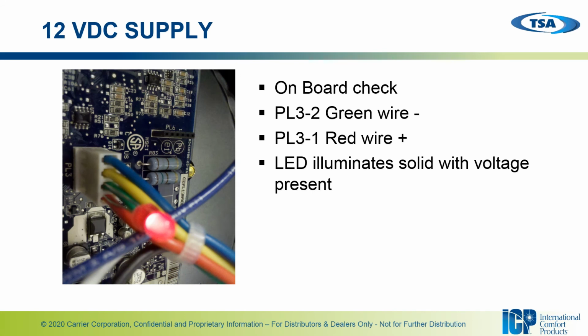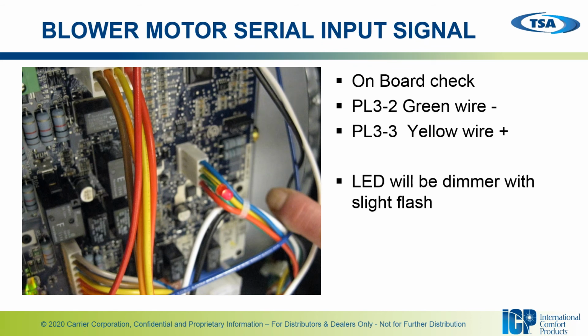So using the LED in the Molex plug, going between your red and green wire, you are going to see the LED illuminate solid with voltage present. Okay, checking the serial input signal, or blower speed signal, if you will. This will be between the green wire and the yellow wire. The LED is going to be a little bit dimmer because you're checking a lower voltage, but you should see a slight flashing in the LED.